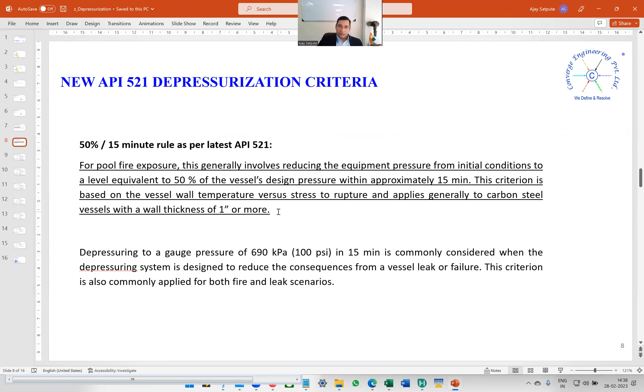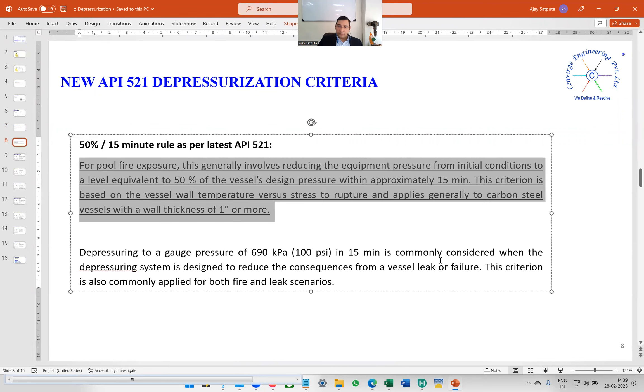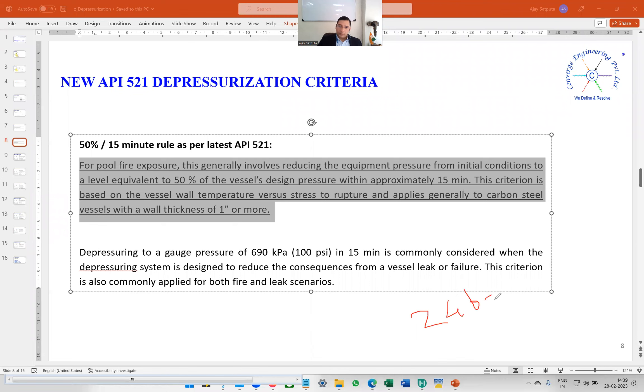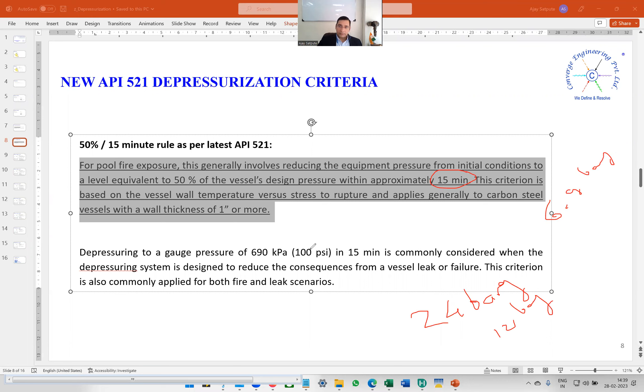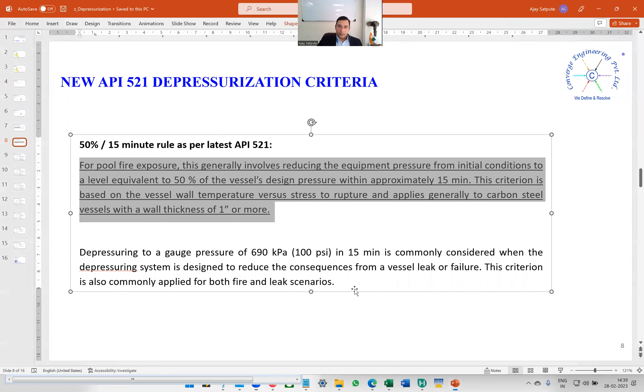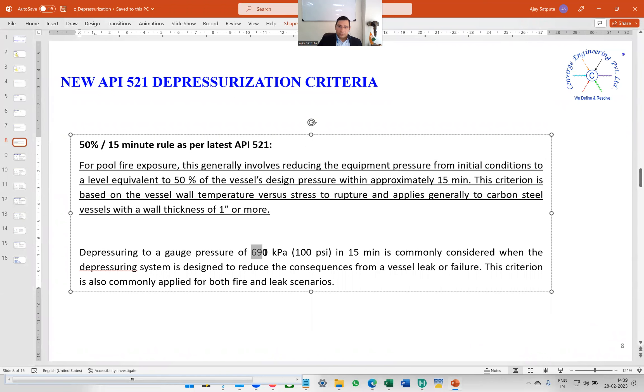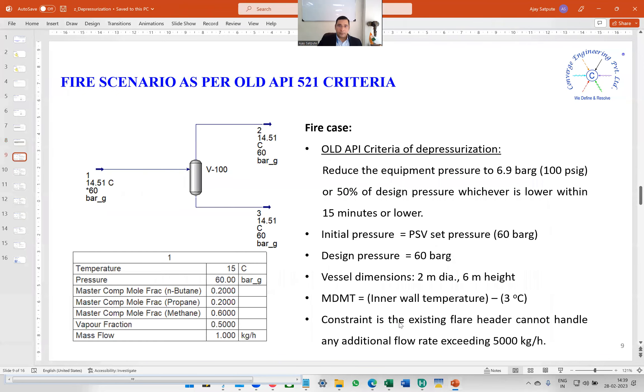The latest API 521 does not talk about 6.9 bar gauge pressure for the fire case. If your vessel's design pressure is 24 bar gauge, you need to depressurize it to 12 bar gauge — 50% of design pressure — in 15 minutes. You don't have to depressurize to 6.9 bar gauge. This is as per the latest API 521. However, for vessel leak or failure, the 6.9 bar gauge criterion is still applicable.